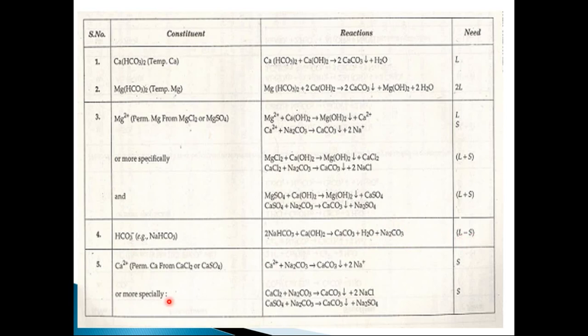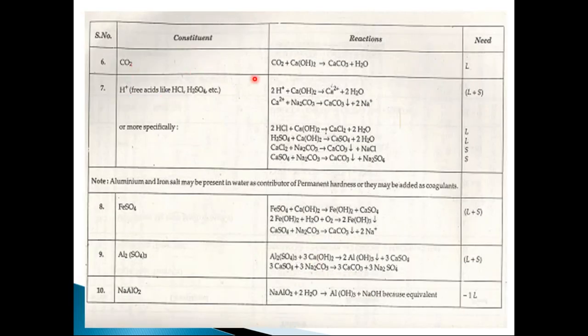For calcium chloride and calcium sulfate (permanent calcium hardness), these react with sodium carbonate to precipitate calcium carbonate, requiring one soda (S). CO₂ reacts with calcium hydroxide to form calcium carbonate, requiring one lime (L). For free acidity from HCl and H₂SO₄, the H⁺ ions react with lime to produce calcium ions, and those calcium ions then react with soda to precipitate calcium carbonate — so one lime plus one soda is required (L + S). For iron salts, ferrous hydroxide is first produced with lime, then ferric hydroxide, and then calcium sulfate reacts with sodium carbonate: overall requiring L + S.